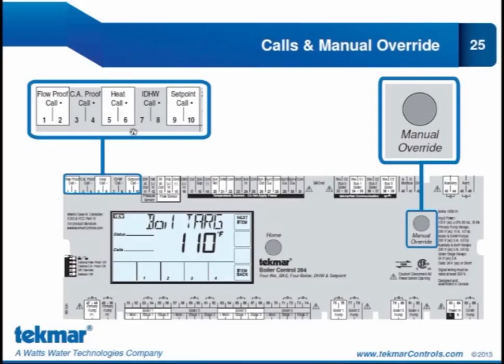We have terminals for heat call. So that can be provided from a thermostat closure. It could be provided from an end switch call. Of course, if we're using tekmarNet communication, we don't need to hook anything up to those terminals. Here we have our IDHW call terminals so that we can connect an aquastat into these terminals. And we have the Setpoint call terminals, so we could connect a thermostat closure into these call terminals.